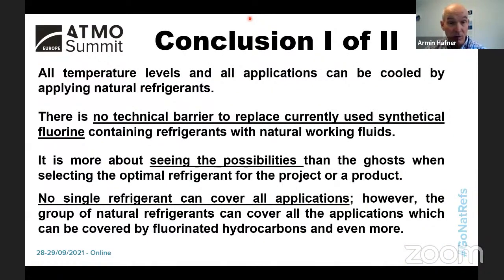However, the conclusion, what is important, is that all temperature levels and all applications can be cooled by applying natural refrigerants. There is really no technical barrier to replace the currently used synthetic fluorine. We can do that. And it's more about seeing the possibilities when you select the refrigerant. It's important that we inform the end user about these alternatives, because the end user, in 99% of cases, chooses the natural one if they get the possibility. And what is also important, no single refrigerant can cover all applications. That's why I showed you there are different alternatives, and we as the designers know when to apply which one.